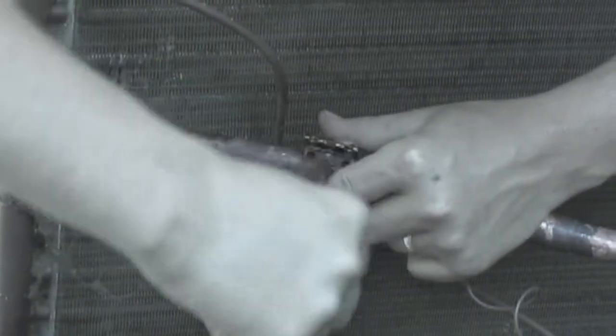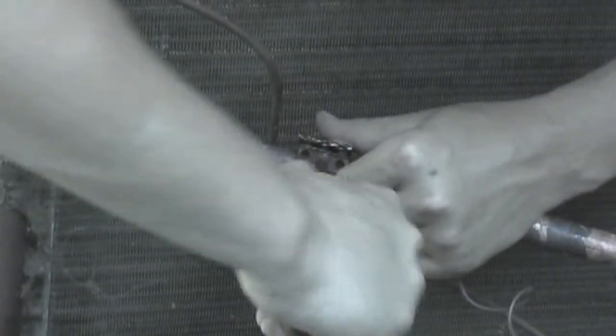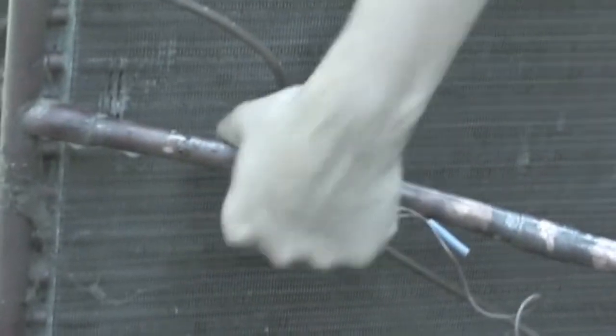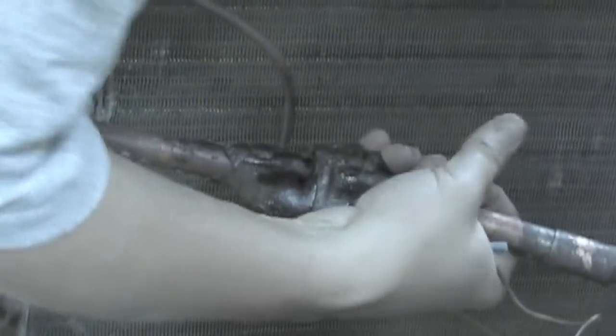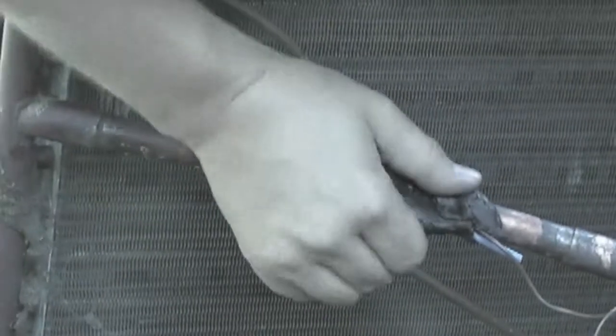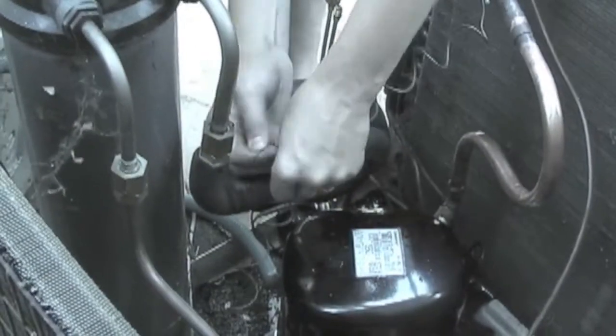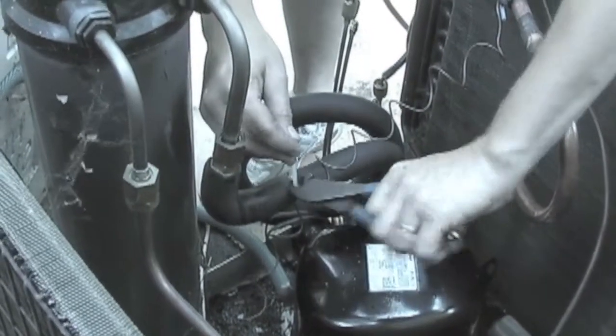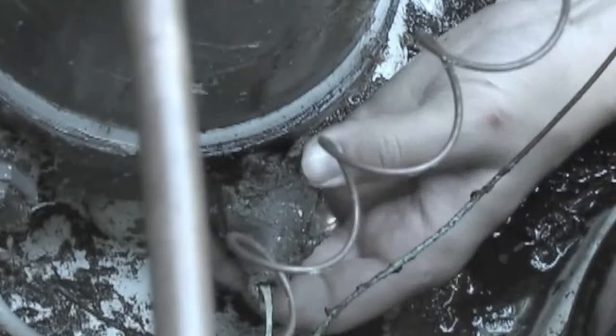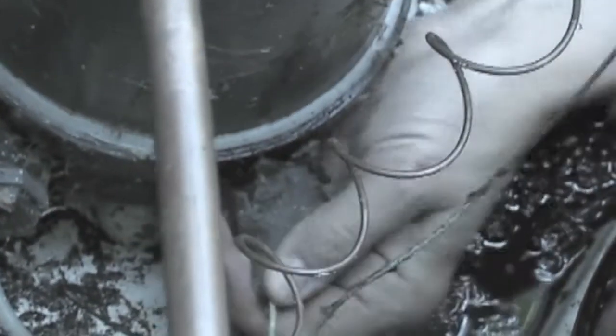Reattach the TXV bulb to the suction line. Make sure that it's on the side of the suction line, not the top or the bottom. Apply cork tape to the TXV bulb to insulate it from the outside air. Secure the capillary to prevent rubbing with other parts of the heat siphon. Reinsert the thermostat bulb into the heat exchanger and insulate it with cork tape.